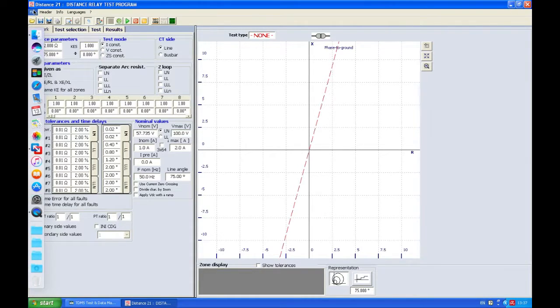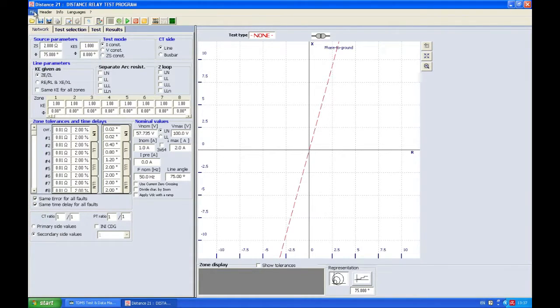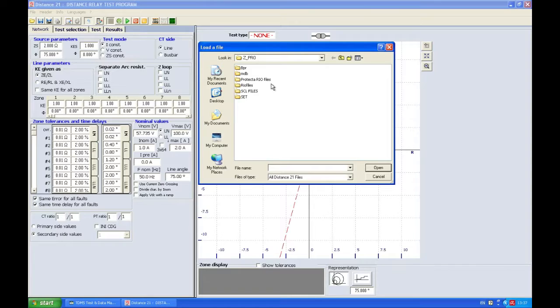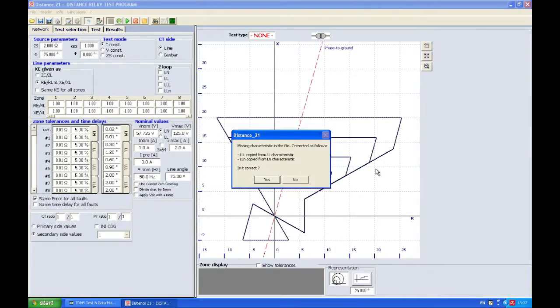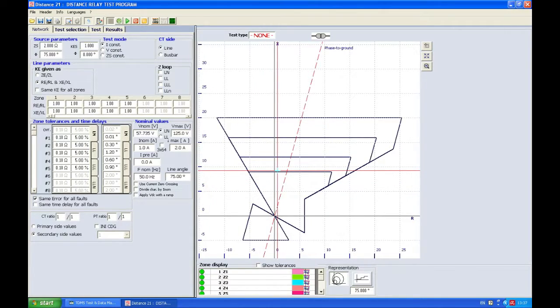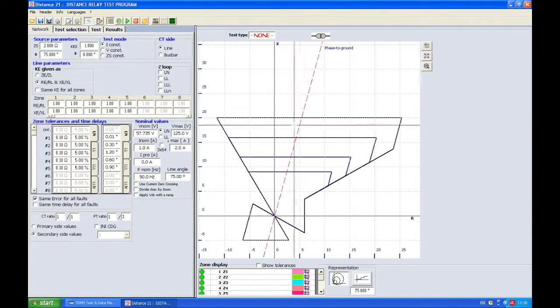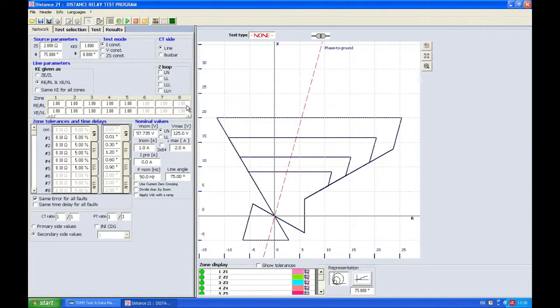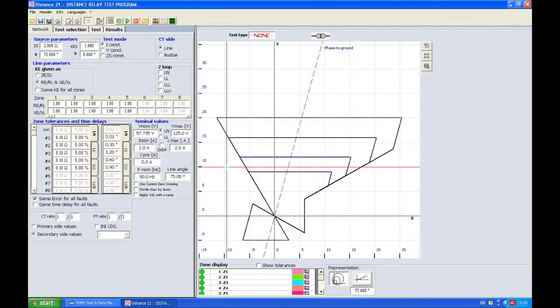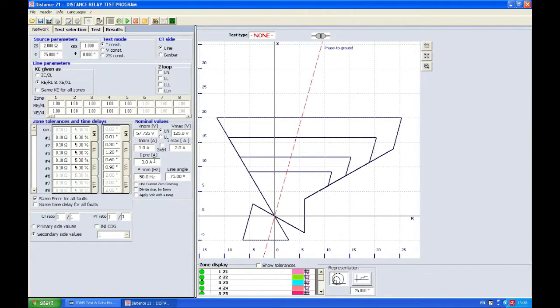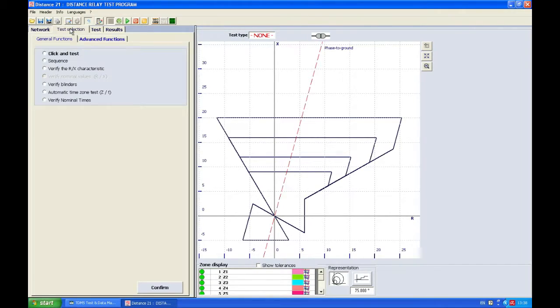I'm opening my relay file which is this one here which I have extracted from my relay, and now I have my characteristic. I see that nominal values are okay. I'm not going to use any pre-fault current. What I'm going to do is go to test selection.